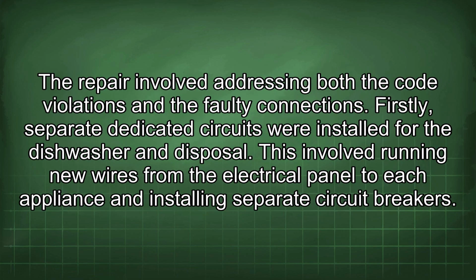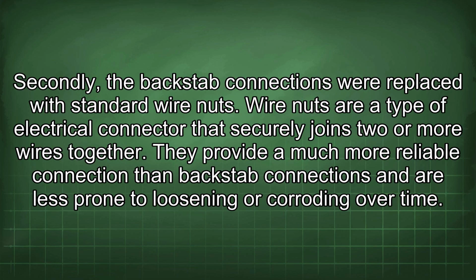The repair involved addressing both the code violations and the faulty connections. Firstly, separate dedicated circuits were installed for the dishwasher and disposal. This involved running new wires from the electrical panel to each appliance and installing separate circuit breakers. Secondly, the backstab connections were replaced with standard wire nuts. Wire nuts are a type of electrical connector that securely joins two or more wires together. They provide a much more reliable connection than backstab connections and are less prone to loosening or corroding over time.